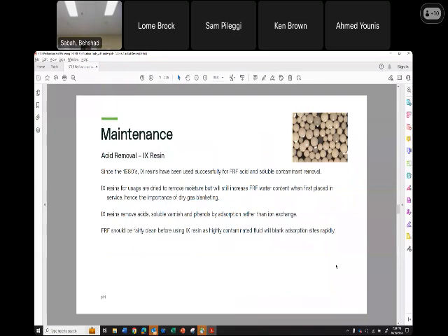And the third technology is IX resin, basically originally used for acid removal, but EPT has combined a mixed bed resin with the goals of increasing resistivity, removing soluble varnish, phenols, etc. So at Pickering, we started using one brand of IX resin back in 2013, and we saw resistivity fall off, and then very shortly after, very rapid darkening of the fluid. And then with the new Hypro skids, we've stopped using that resin.